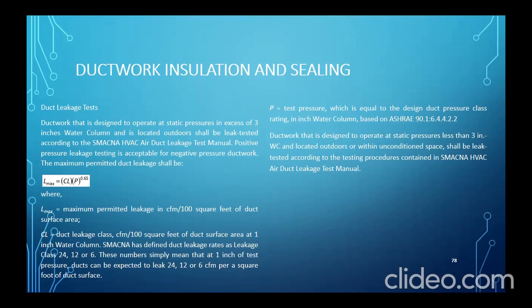L is the maximum permitted leakage in CFM per 100 square foot of duct surface area. So CL is the duct leakage class, CFM per 100 square foot of duct surface area at 1 inch water column. SMACNA has defined duct leakage rates as leakage class 24, 12, or 6. So these numbers simply mean that 1 inch of test pressure duct can be expected to leak 24, 12, or 6 CFM per square foot of duct surface.